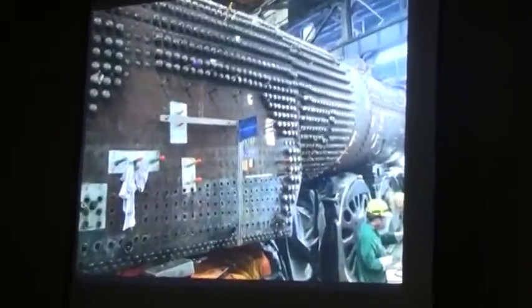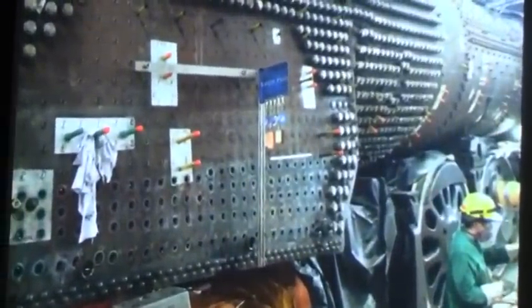The drain to that telltale should go down below the level of the boiler and deposit that water where it can just get on the trailing truck or down on the track. And regretfully, it was depositing into the back part of the boiler, and as I said, going through those telltale holes. So as we started to take the firebox apart, we peel back that fire brick, and when we're done talking, you can come up and look at the plate. That's what we discovered. Bearing in mind that that plate has to withstand 300 pounds per square inch.